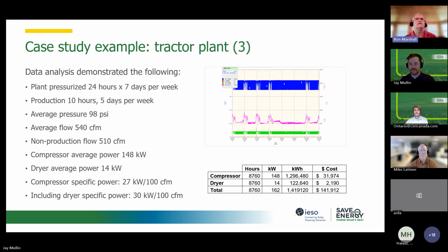So we can see some charts. We can see the typical sawtooth waveform, the fuzzy blue line at the top of the chart, that tells us how heavily loaded the compressor is. On the pink line, there's a moving average that I put on there. We can see when the flow is being consumed and when not. And we can see on the green at the bottom how much, in this case amps, which we converted to kilowatts, were being consumed by those compressors.